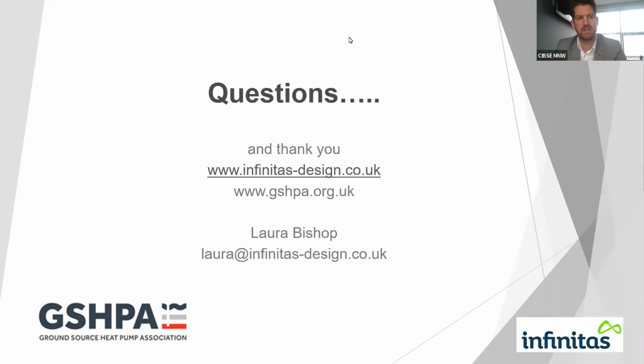A question from Mike: are there currently any air source or ground source heat pump solutions available for industrial type buildings? Oh, yes, absolutely - the ones I showed earlier, big commercial heat pumps by people like Clade, Carrier, Trane, and lots of others, are industrial heat pumps specifically for large commercial and industrial buildings. For example, I showed the big glasshouses earlier, but you could have a factory doing some kind of process load. I'm willing to be shot down, but so far I'm not aware of any heat pumps that go above 100 degrees C - you're limited to about 95 degrees C for process heat. But yes, you can get both air source and ground source up to those temperatures, and up to 10 or 20 megawatts.